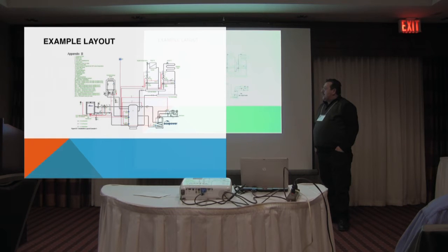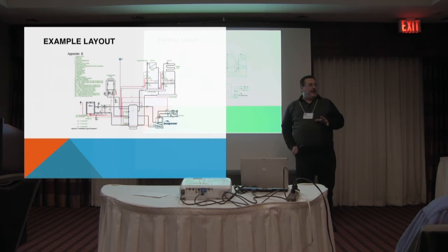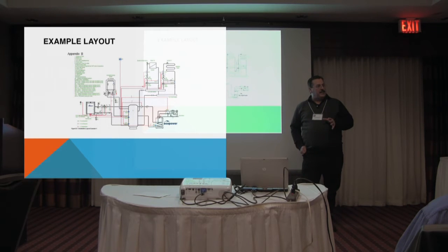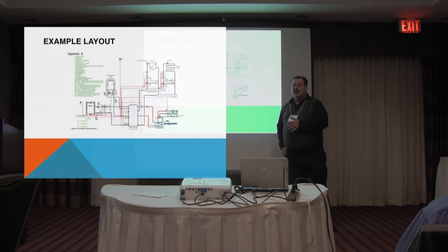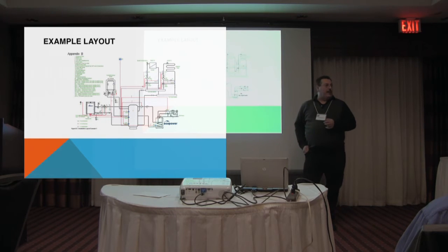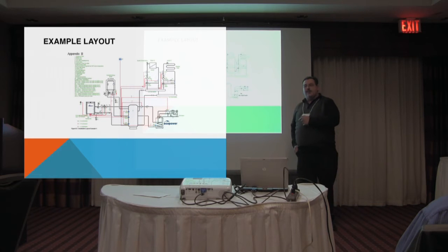In two installations that we've supplied, they're heating not only radiant floor and domestic water, they're also heating an outdoor pool, and they're heating a hot tub as well. That's a perfect application in a residential system where you have an annual thermal load. You've got a load all summer long, right? Now you can keep this unit running. The more this unit runs, the more money it's going to save.